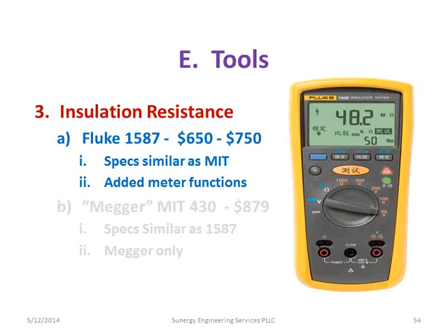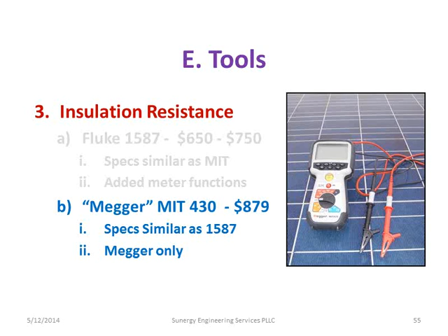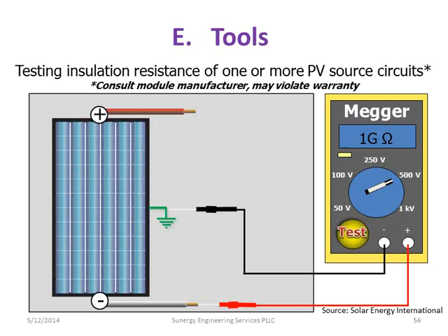so you can do it with either one. Again, the issue with this is that it's really not as safe to test a string in a module with this. I mean, you can do it. There are some module manufacturers that don't like you to do it, so you have to be a little bit careful about that. And again, the problem we just talked about earlier, that voltage is going to add, and if there's a short in the system actually that you're looking for when you're doing an insulation test, you could possibly damage some of the components.